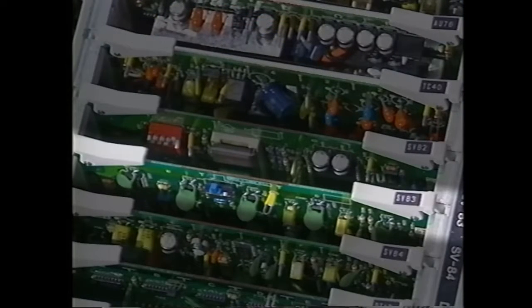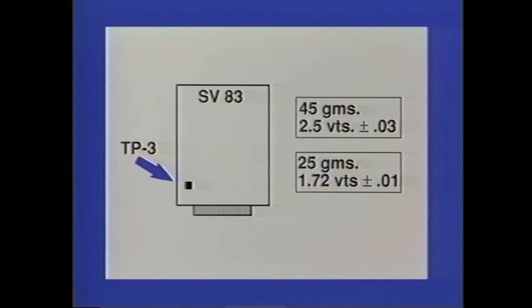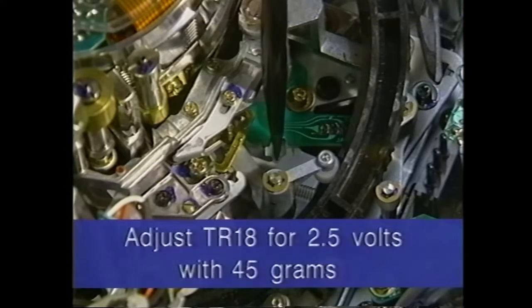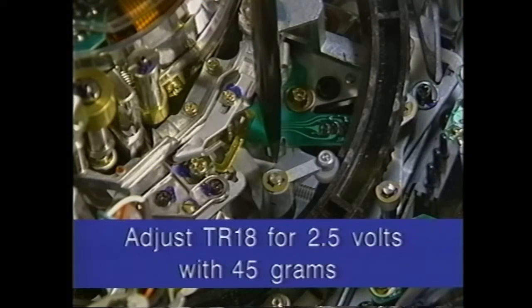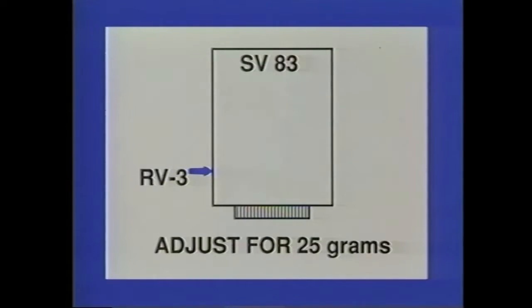Voltage, measured at TP3 on the SV83 board, should be 2.5 volts when 45 grams is applied, and 1.72 volts when 25 grams is applied. Adjust the TR18 board if the 45 gram reading is out of specification, and adjust RV3 on the SV83 board if the 25 gram force does not produce 1.71 to 1.73 volts.